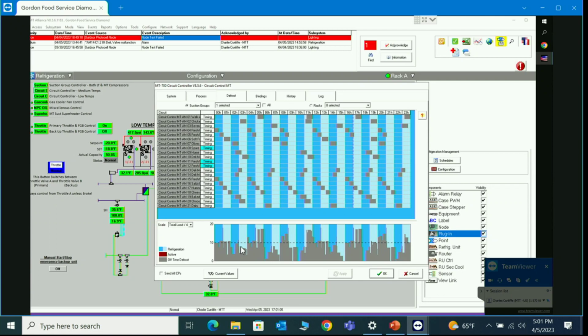And my advice to you, just in case, is do backups frequently, and then just like you can take a file out of Windows, you can take that backup and make a copy of it and put it on a USB drive, your latest and greatest backup. Let's say something happened to that data logger and you have to replace it. Now you've got the backup in a fire safe. You put it into the new data logger that we ship to you overnight, and depending upon how big the store is, in anywhere from maybe 2 hours to 6 hours, you can rebuild that whole system from the backup that you have on that USB drive.